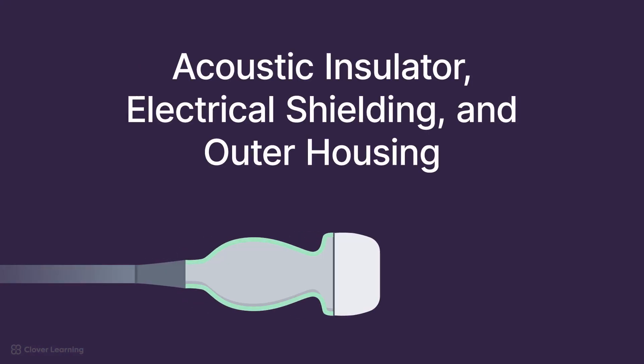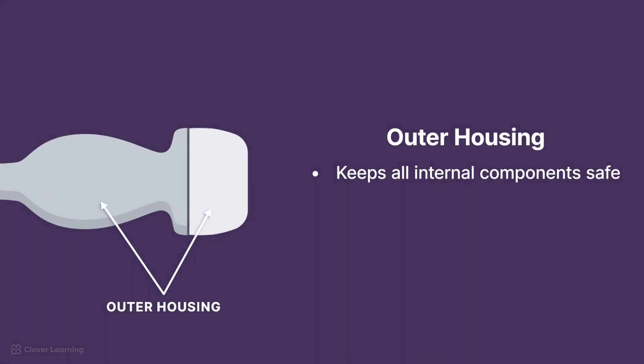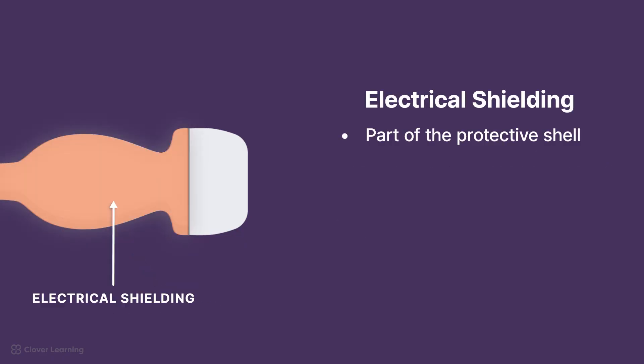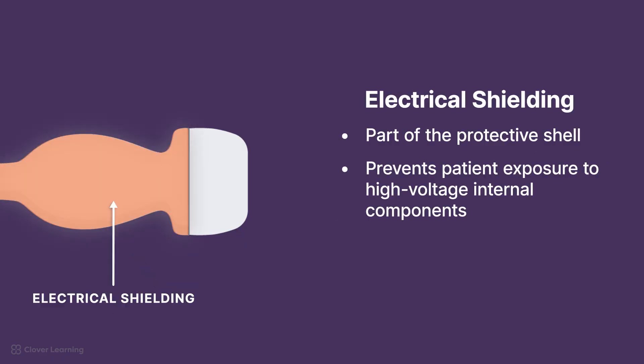The final components of all transducers encase its inner components and are the acoustic insulator, the electrical shielding, and protective outer housing. The outer housing keeps all the internal components safe from wear, tear, and contamination, ensuring the transducer performs at its best and provides a smooth, safe surface for patient contact. Part of the protective shell is the electrical shielding, which prevents patient exposure to high-voltage internal components and reduces outside electrical interference.